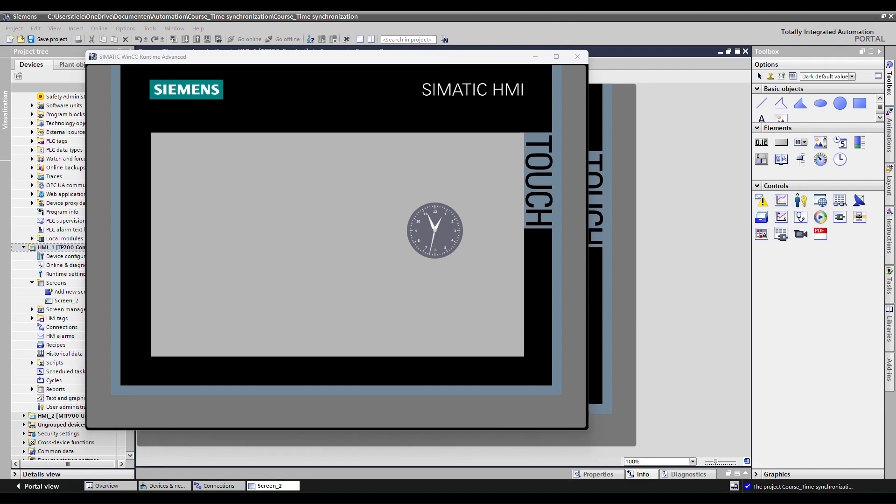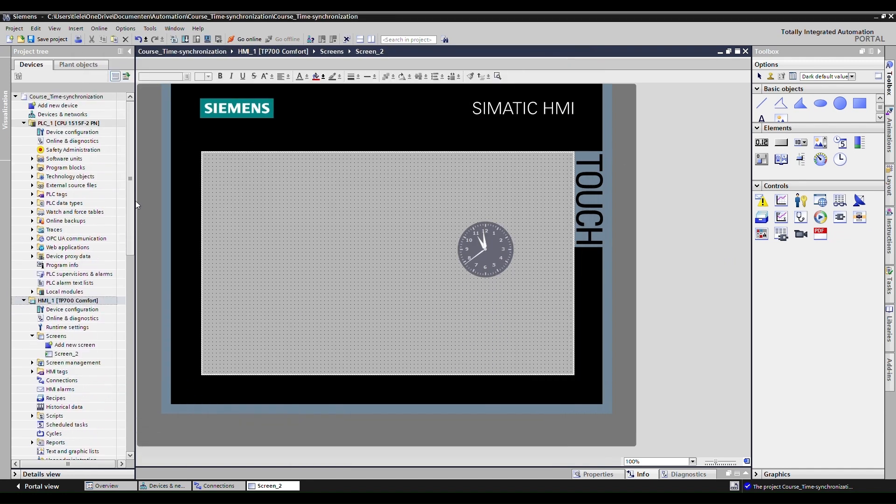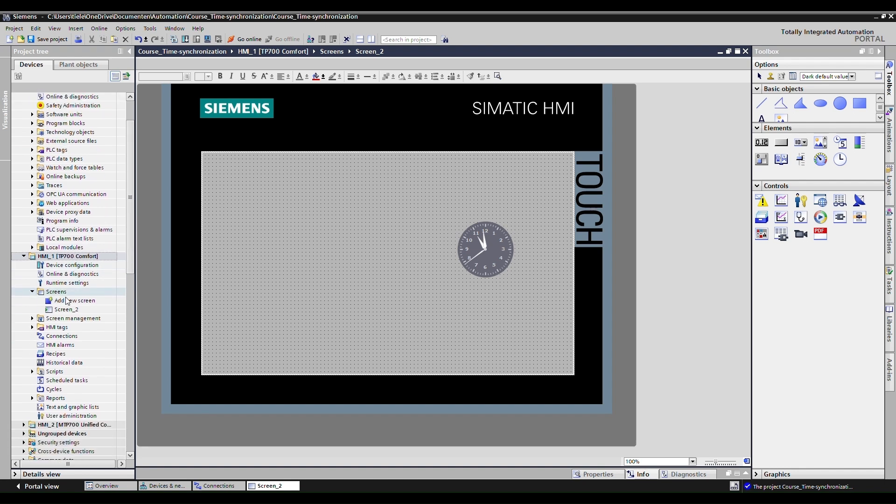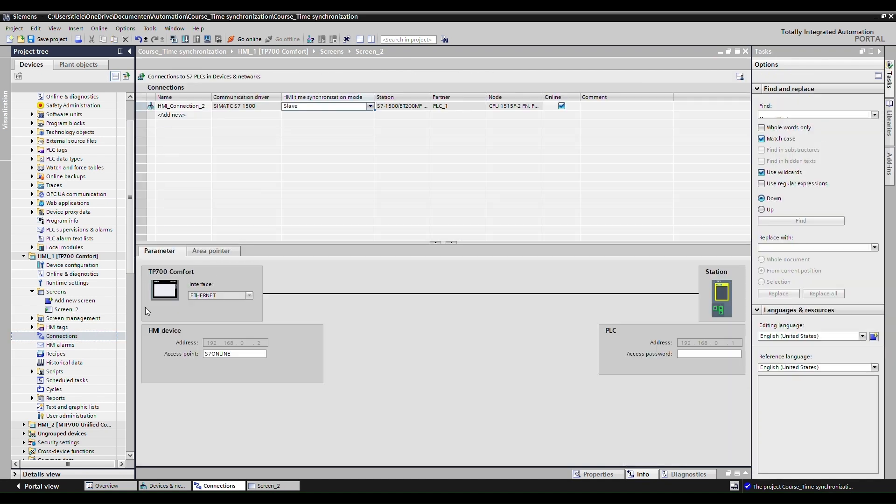I should mention that this time synchronization that we're using now. So as we're using a 1500 PLC with a comfort panel HMI, this time synchronization is possible. So this is also possible with S7-1200 series, but otherwise you will have to look at the area pointers and use those as the HMI time synchronization mode won't work as expected.